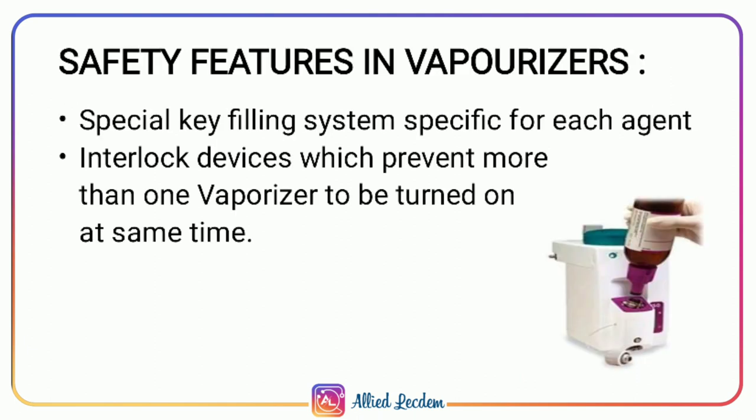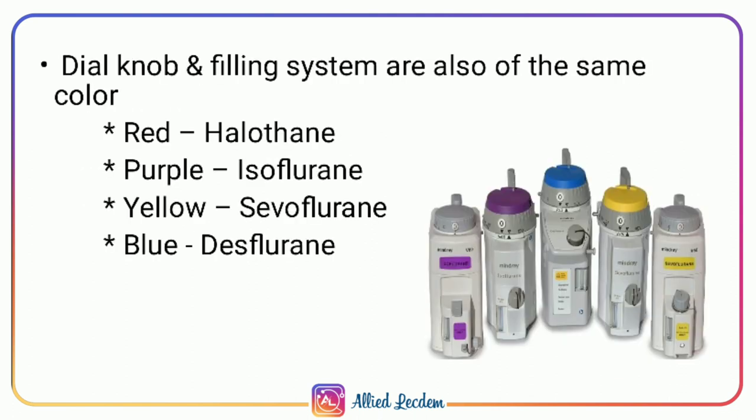Safety features in vaporizers include a special key filling system specific for each agent, and interlock devices which prevent more than one vaporizer from being turned on at the same time. The dial knob and filling systems are also color coded: red for halothane, purple for isoflurane, yellow for sevoflurane, and blue for desflurane.